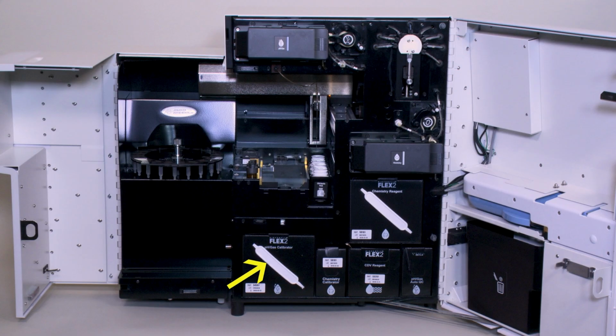Inside of the FLEX 2, you will find all of the reagents and calibrator cartridges, sample probe and transport arm, 96 well plate dock, well assembly, pH and gas sensor module, pH and gas pump, chemistry sensor module, optional osmometer module and carousel, chemistry pump, syringe pump, pH and gas auto QC ports, refrigerated chemistry QC bottles, and sample cup waste container.